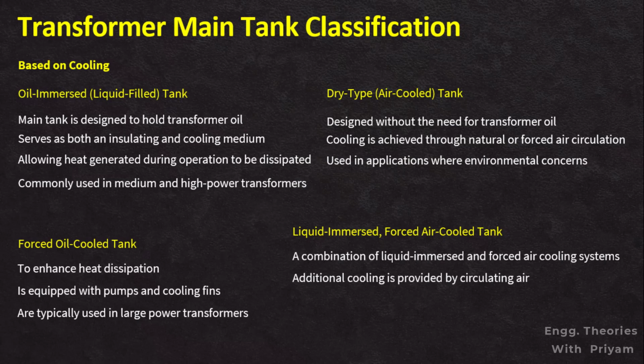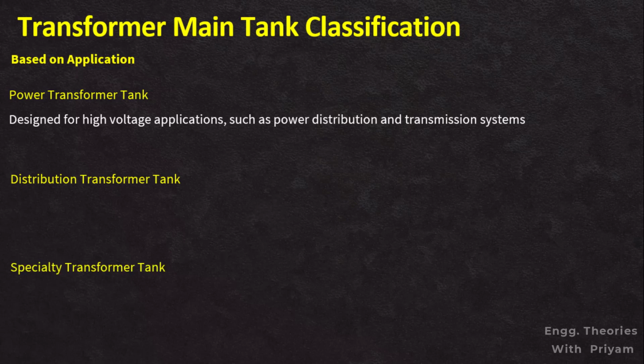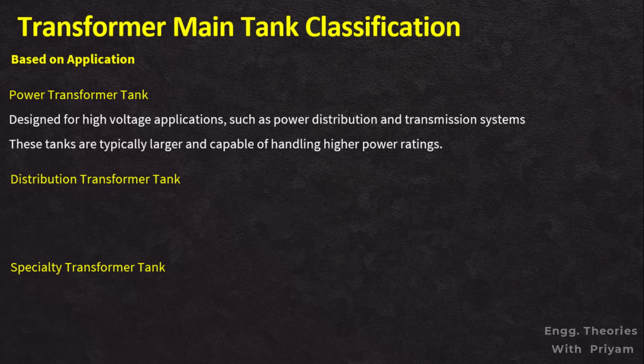Additional factors: sizing and capacity. Transformers come in various capacities with the tank design adapting to accommodate the specific needs. Application: different applications such as power transmission and distribution might have specific requirements for tank features like the cooling system. Based on application, the transformer tank can be of three types: power transformer tank, distribution transformer tank, and specialty transformer tank. Power transformer tank is designed for high voltage applications such as power generation and transmission systems. These tanks are typically larger and capable of handling higher power ratings.